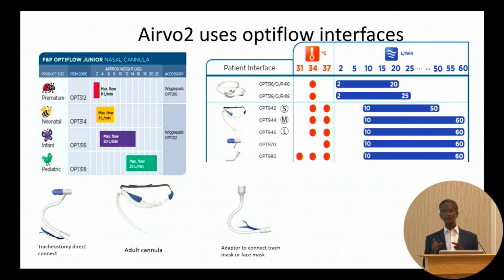It is important to know, in contrast to CPAP, which is totally leak proof, meaning you need a tight fitting nasal mask or full face mask without a leak, that when you are using high flow, you need to have a leak. It is a partially open system. So the cannula fitting is an extremely crucial part. You have to select the size of the cannula that obstructs only 80% of the nares.